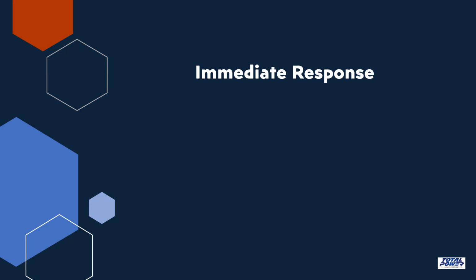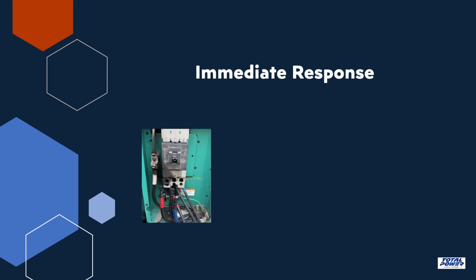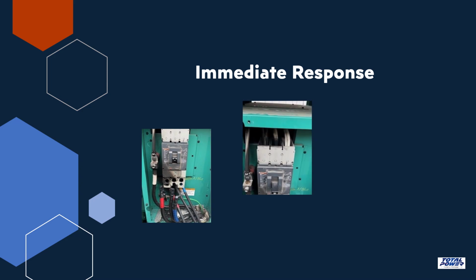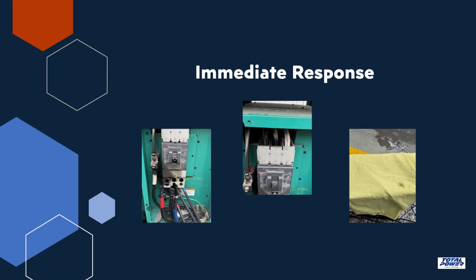The area was immediately secured. No additional work was permitted. The unusual smell directed attention toward the generator breaker. Inspection revealed that the generator breaker had experienced an internal electrical failure. An arc flash had occurred inside the breaker enclosure.